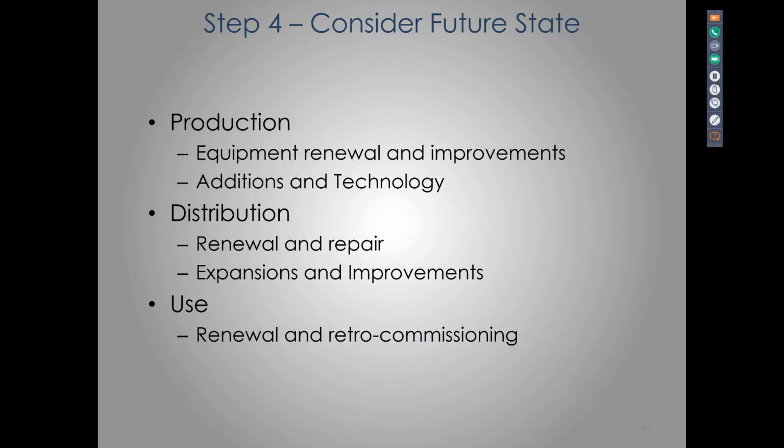Just to wrap this one up, again, don't ignore the use. One of the ideas is renewing building equipment: replacing air handlers, heat exchangers, retro-commissioning buildings. It's been remarkable the magnitude of savings that have been achieved by investing in aging buildings. Once you've achieved that savings, it lowers the demand on the utility system and on the plant. So retro-commissioning a building ultimately buys you more time before you have to invest in the next boiler or chiller, because you just freed up some capacity. You're not using so much anymore.